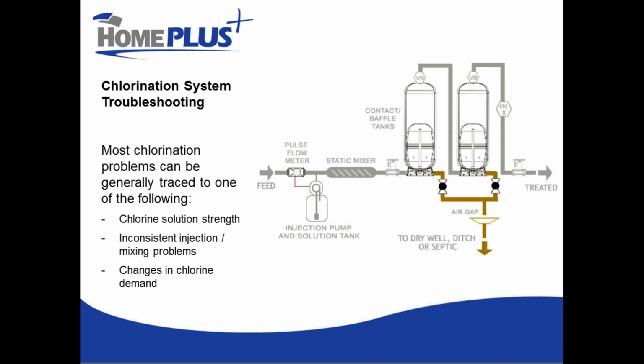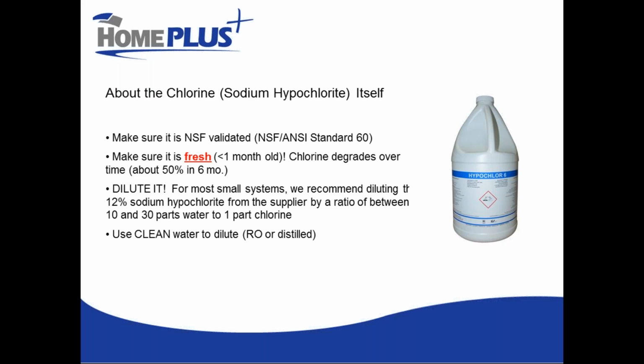So typically, we're going to have a problem with our chlorine solution strength. We're going to have inconsistent injection or mixing, or we're going to have changes in our chlorine demand. Those are the main things that cause grief for us in chlorination systems. So as I said, chlorine is not all created equally, and nor does it stay equal. So we need to pay attention that when we buy chlorine, we're always buying the same strength. You know, if you buy 12% and put that in your solution tank today, and then next time you buy chlorine, you buy 6% strength, and you put that in your solution tank, you should not expect the same results.